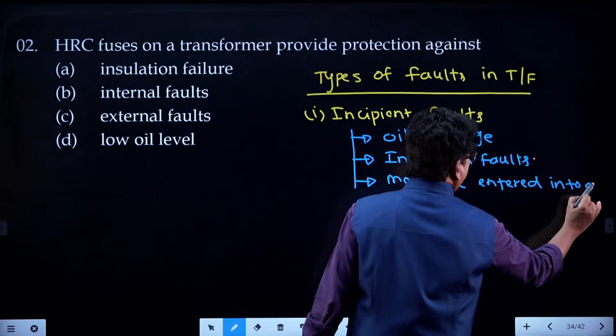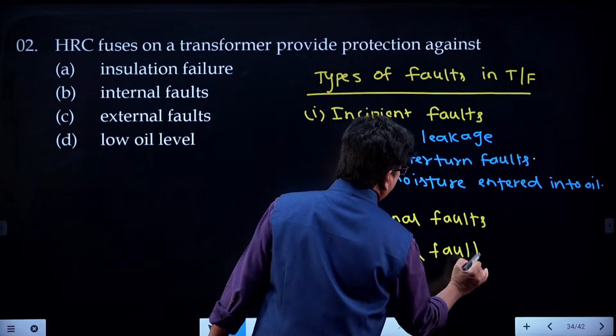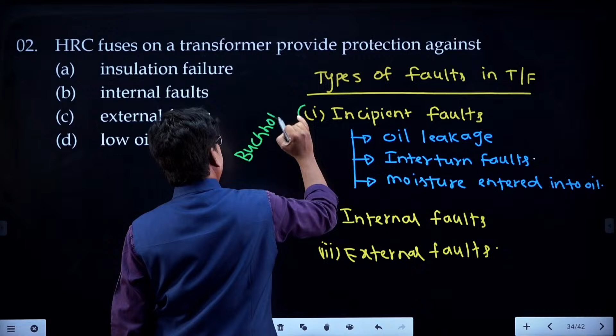The second type of fault is internal faults, and the third type of fault is external faults, outside of the transformer, right? For incipient fault protection, definitely we have to use the Buchholz relay. For internal fault protection, based on the rating, for small rating we can use the Buchholz relay. For large rating we have to use the percentage differential relay. That is called merz-price protection of the transformer.